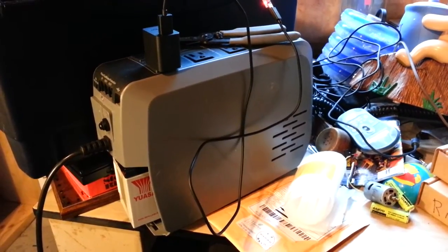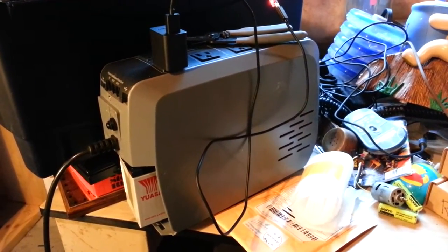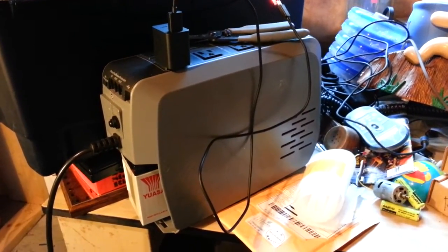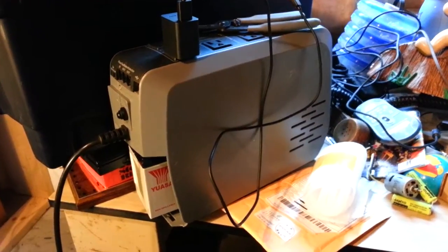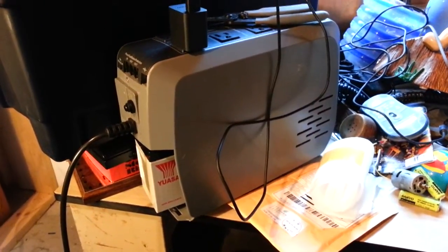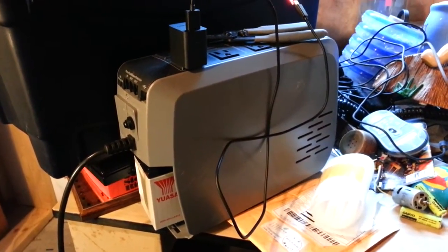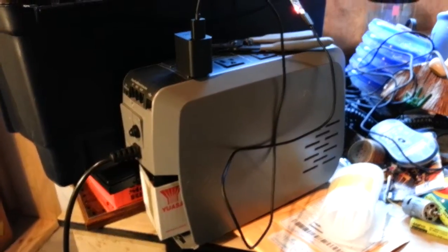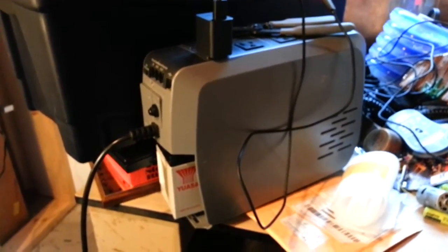...these Belkin UPS units will not start up, regardless of the voltage state, regardless of whether or not there's a battery inserted. If the voltage state is too low or reads zero from the battery leads, it will not start.